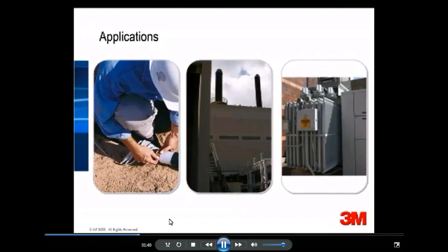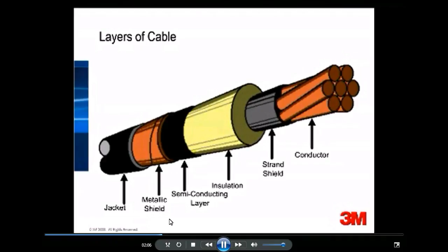Medium voltage cable is what is commonly used throughout electrical distribution systems, power plants, and industrial facilities, such as oil and gas production facilities. It is also what is used to bring power to our neighborhoods, schools, malls, and offices. There are 6 distinct layers in medium voltage cable. They are conductor, strand shield, insulation, semiconducting layer, metallic shield, and jacket. Each of these layers is critical to the cable system. You can click Next to continue, or click on a specific layer to jump to an explanation.